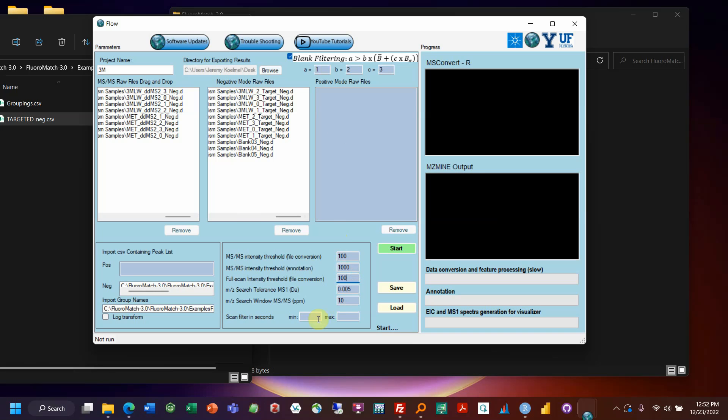Depends on where your noise level is. So pretty much this is the noise level to reduce file size. Another way you can reduce file size is changing the min and max in seconds. So let's say your void volume is at 1 minute, you don't want to look at anything below that. So here you can put 60 as your min. And maybe you know there's an equilibration time that you acquired that you don't care about after 10 minutes, so you can put 600 here. And that way it will cut your files down. Again increase the speed of analysis and decrease the file size on disk. Less likely to crash too.